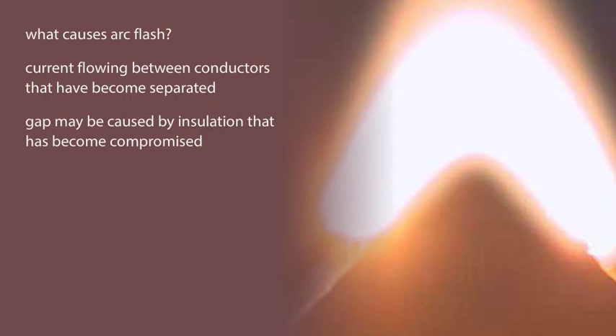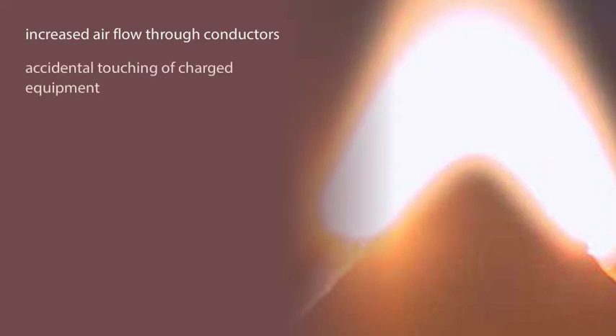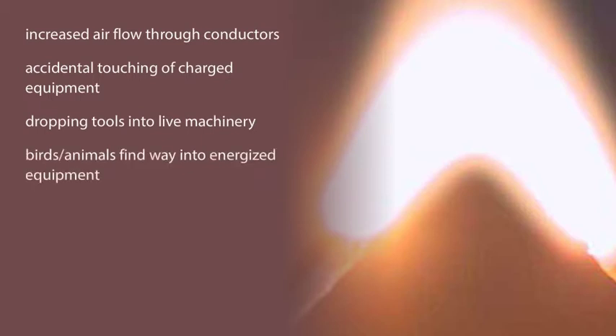Arc flash may be caused by excessive conductive dust or corrosion, increased airflow through conductors, accidental touching of charged equipment, dropping tools into live machinery, or birds and animals that find their way into energized equipment.